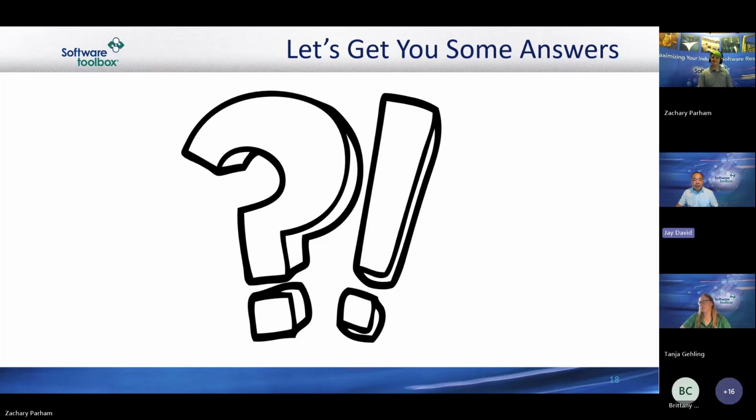Let me start, Zach, with just a run through of what are the pros and cons of using a standalone LGH File Inspector as opposed to the industrial graphic version. Yeah, so the pros of the standalone LGH File Inspector desktop application. You can script at this time, which is not currently possible with the industrial graphic. So if you want to automate your querying, that can be done through batch files, through Windows Task Scheduler, through InTouch. And the blog I mentioned earlier, we have blog posts for all three of those to kind of help you get through them.